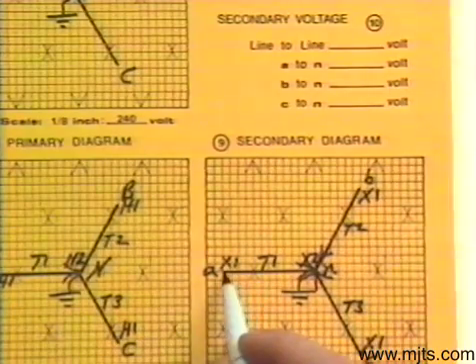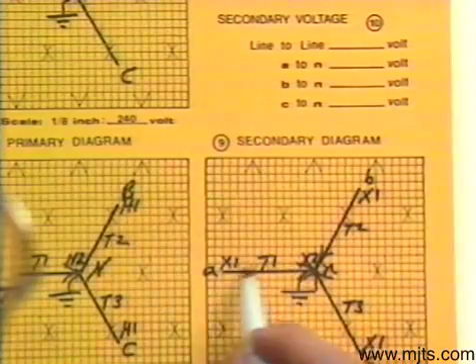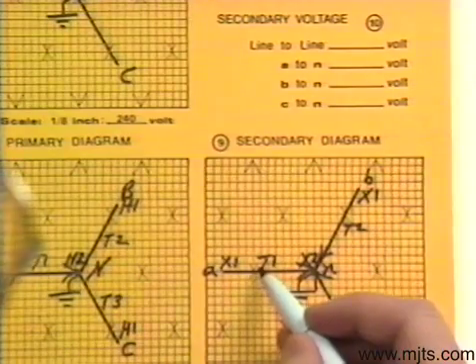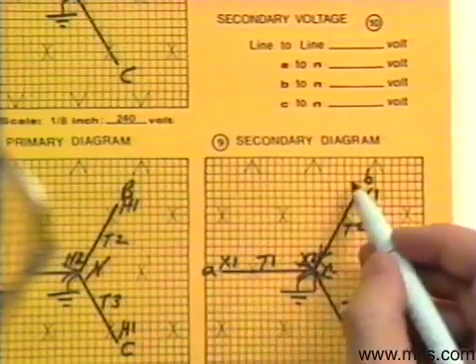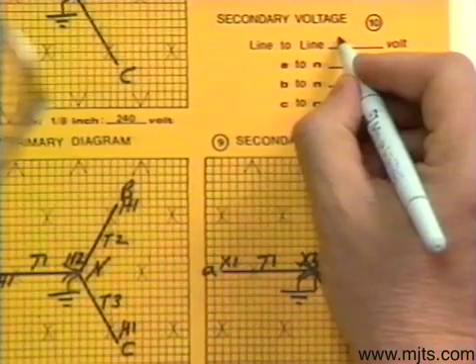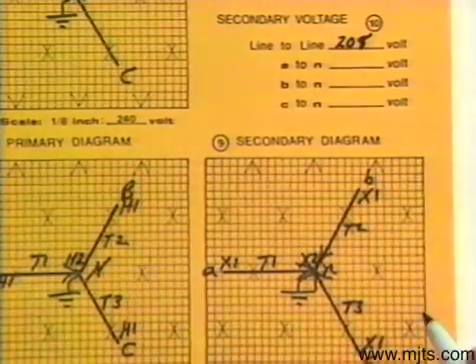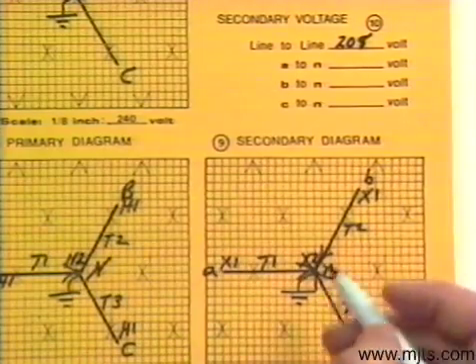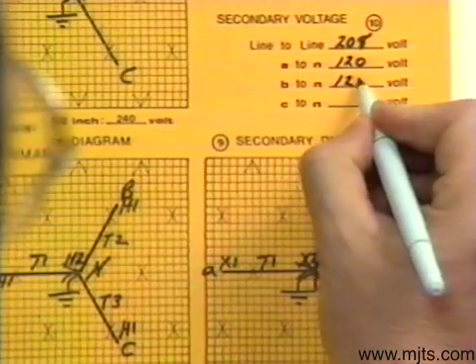Using our 3-phase constant: we have 120 volts to ground, so multiplying by 1.73 gives us the phase-to-phase value of 208 volts. From line to line we'll have 208 volts, and phase-to-neutral on all three phases we'll have 120 volts.